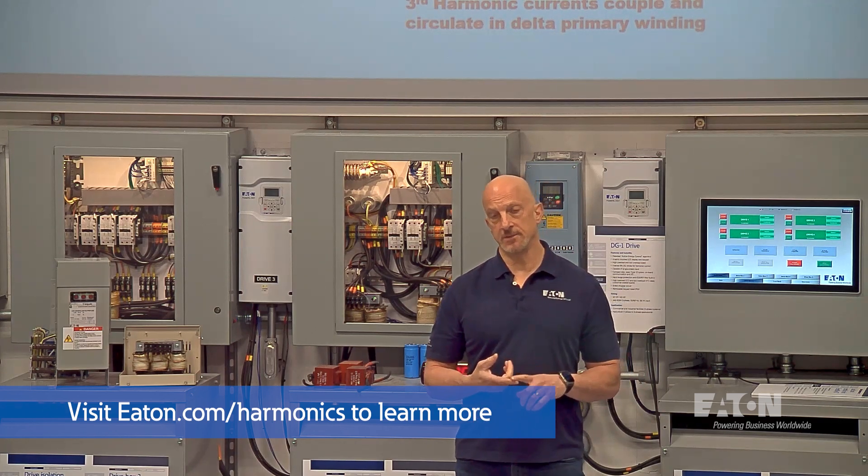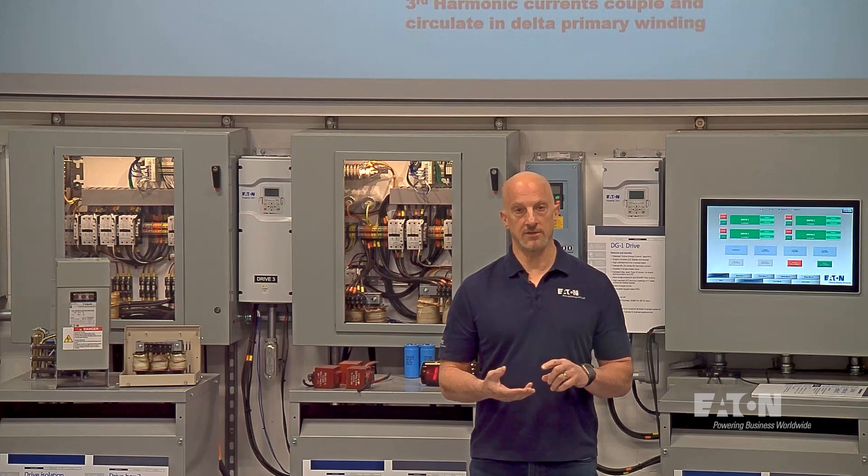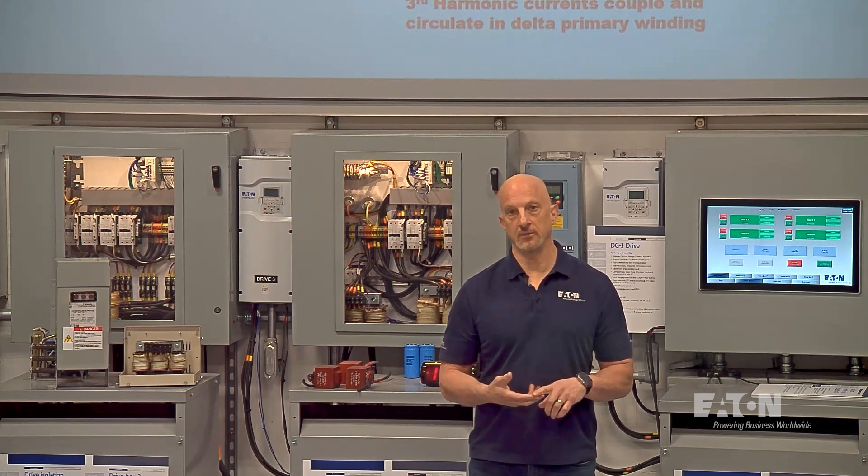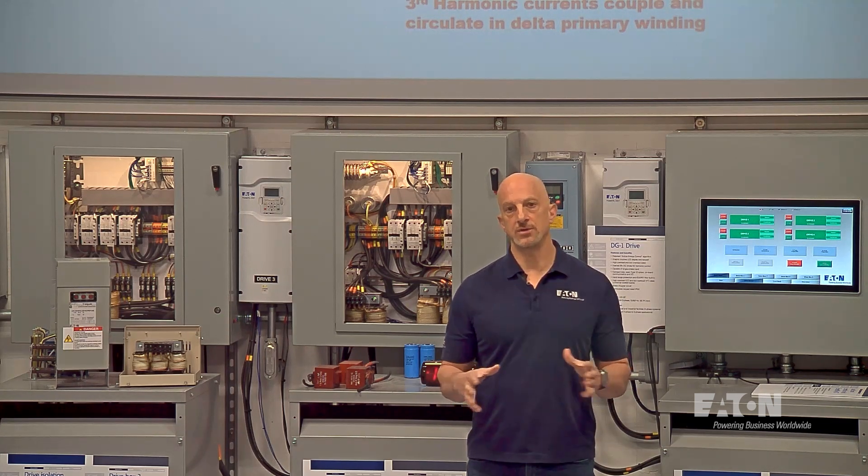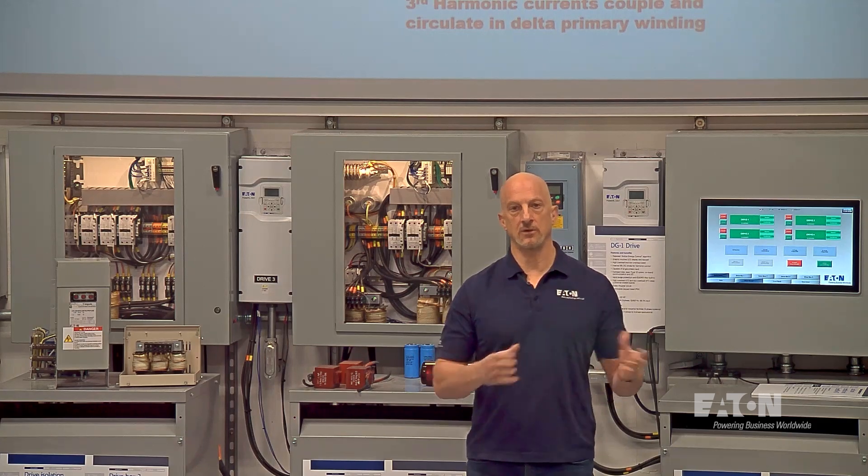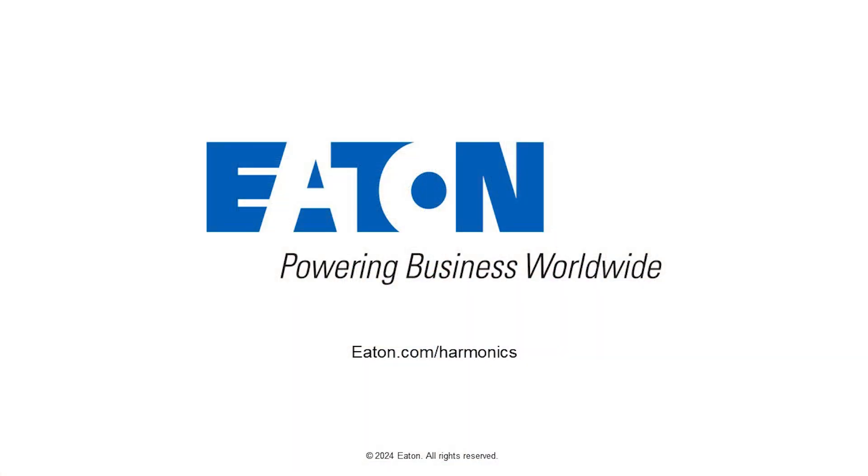But all the other harmonics, typically, the fifth, the seventh, which are negative and positive sequence, or the fundamental, all those should add up to zero if you have balanced current on each phase.